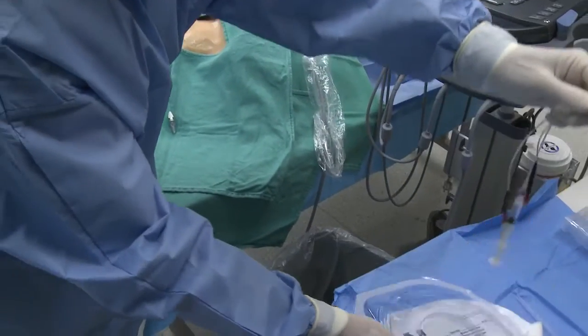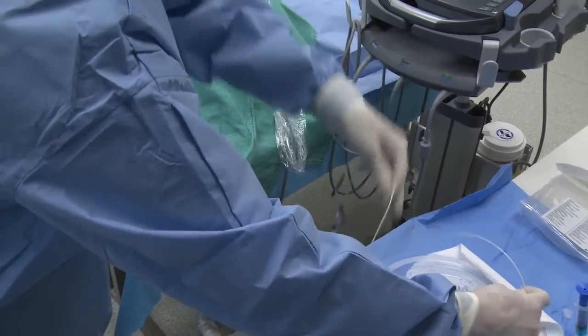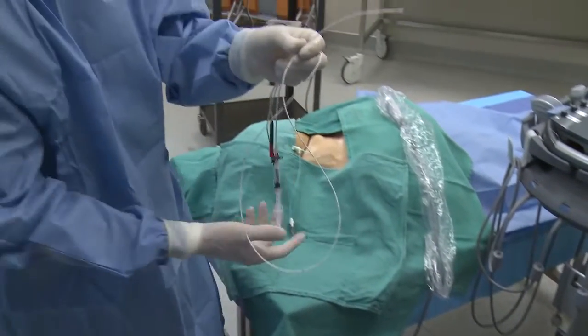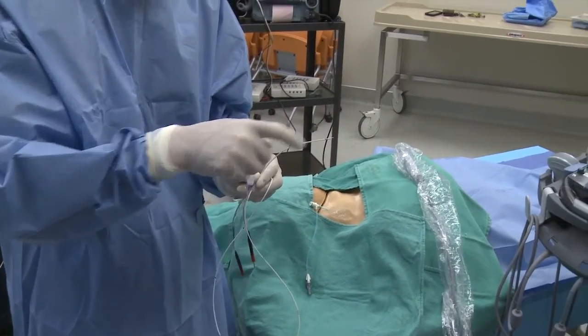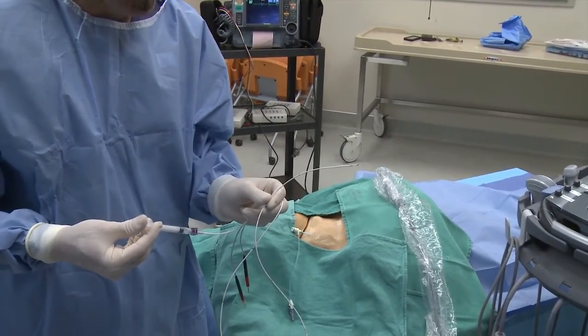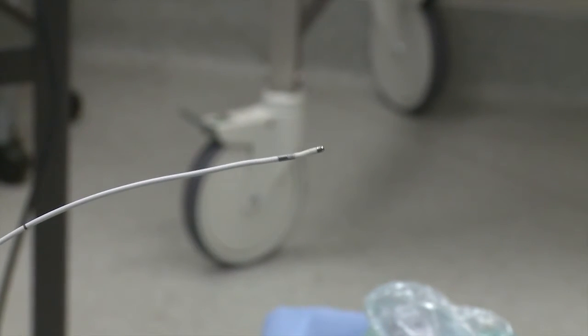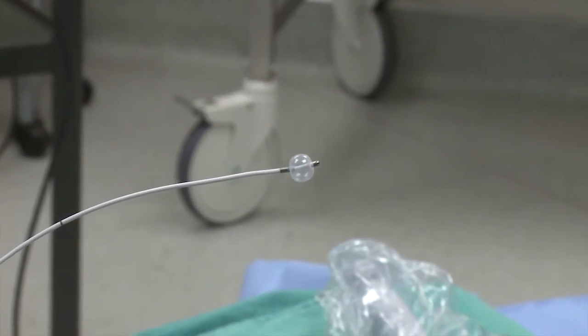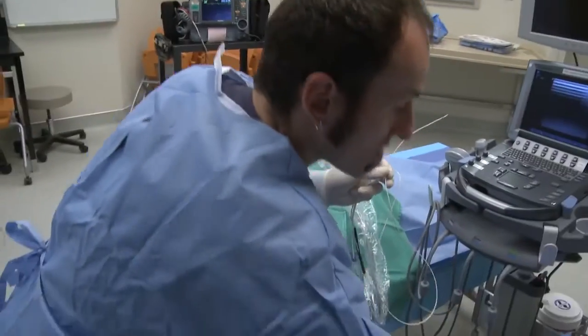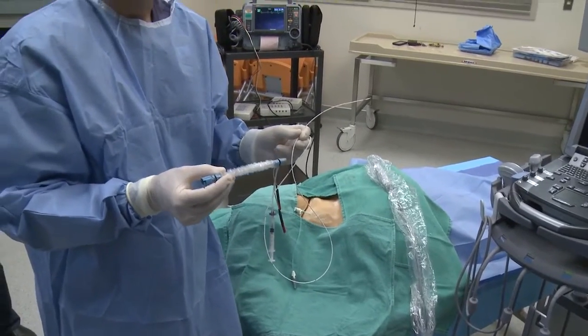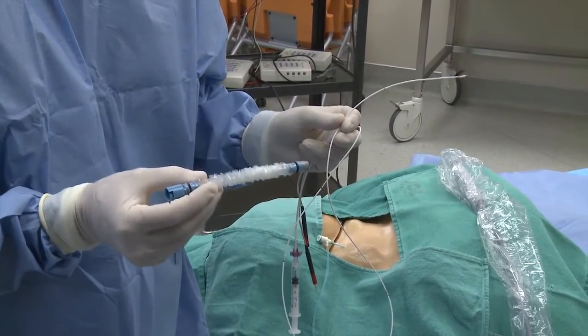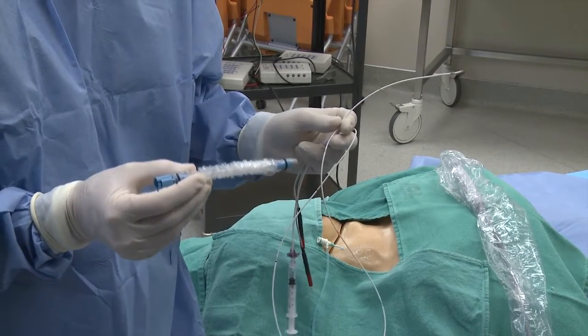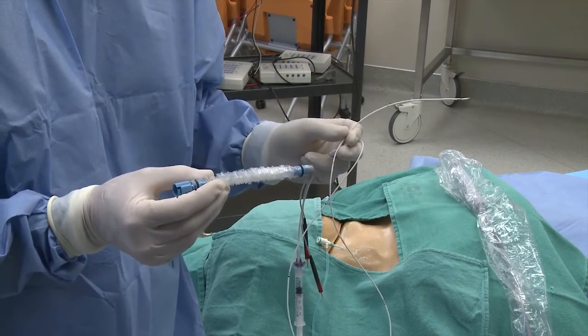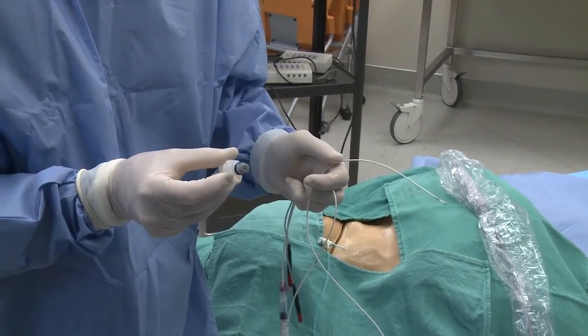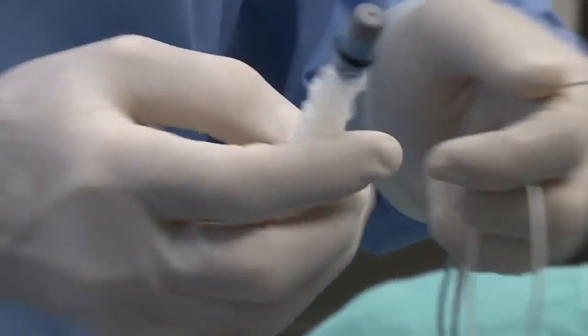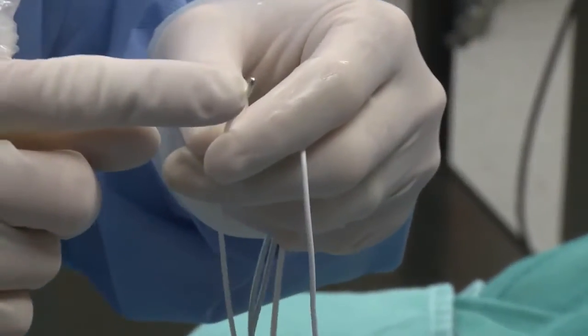Now, you're going to take the pacemaker wire out of the container. At this point, I like to ensure that the balloon on the end of the pacemaker wire is able to be inflated. And it is. Make sure that the balloon inflates on the pacemaker wire. A crucial step now is to make sure that you place the pacemaker wire cover on the pacemaker wire. If you forget to do this, it's going to be impossible once it's inside the patient itself. The gray end with the small hole goes over top of the end of the pacemaker wire.